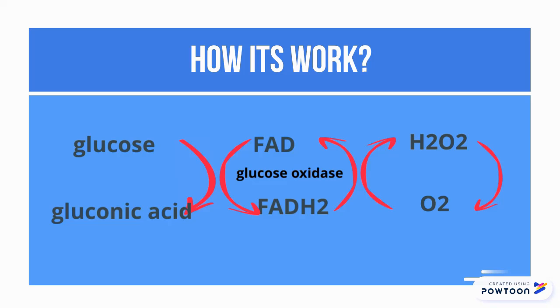After the glucose and oxygen react with the glucose oxidase to form gluconic acid, only the oxygen remaining will penetrate the second membrane of the biosensor to be measured by the electrode. This will produce electric current. A lower electric current reading indicates a higher concentration of glucose present in the sample.